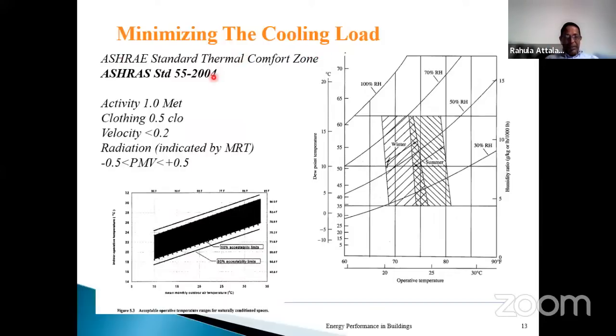The standard that deals with this is ASHRAE standard 55, which talks of thermal comfort. Thermal comfort can be under air conditioning using mechanical cooling, or it can be comfort related to ventilation, but without using a mechanical device. So these two diagrams represent the standard. Some of you at least might be familiar with the psychrometric chart, where the standard says, for a standard activity, that is normal activity, measured in MET, the activity that converts the energy that you have in your food into heat, then the clothing level, that is the clothing resistance, the velocity inside the building, and the radiation of the surfaces around you, that's the walls, the windows, etc.